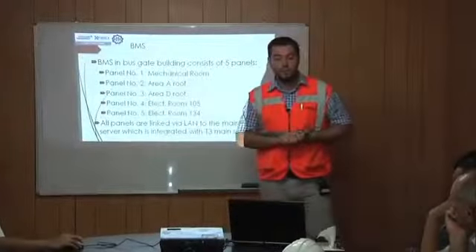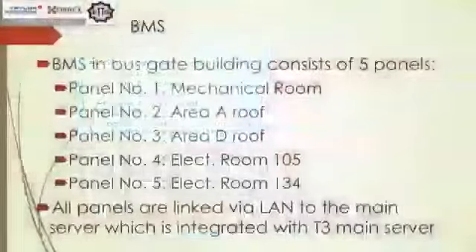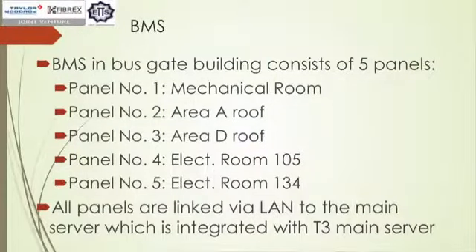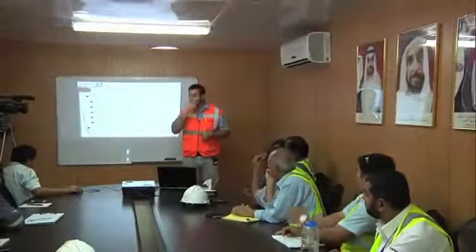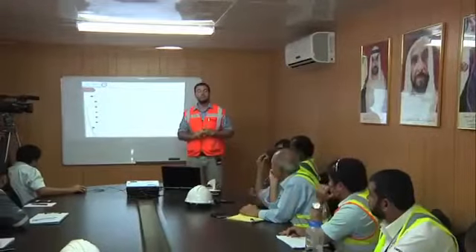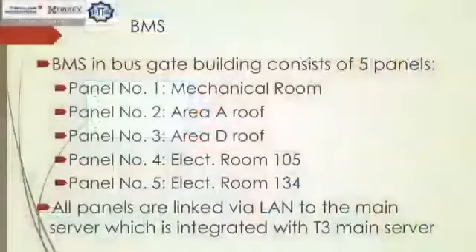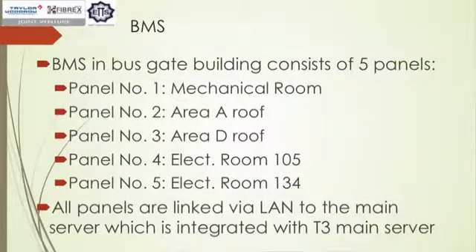So we've got 5 DDC panels for the BMS in our system. We've got panel number 1 for the mechanical room. We've got panel number 2 for roof area A, which controls 2 RTU units, RTU2 and RTU3. We've got one panel located in area D. It controls the RTU1 and RTU4. We've got one panel in the electrical room 105 and another panel in the electrical room 134.